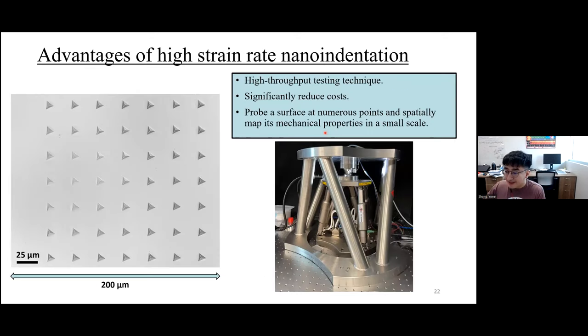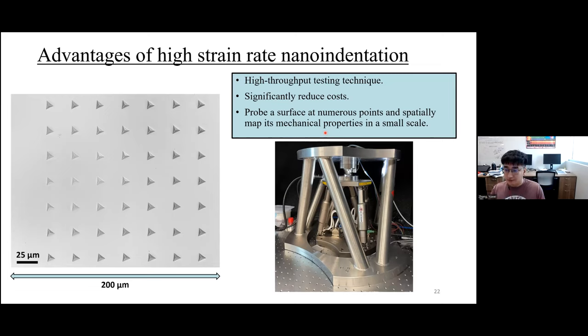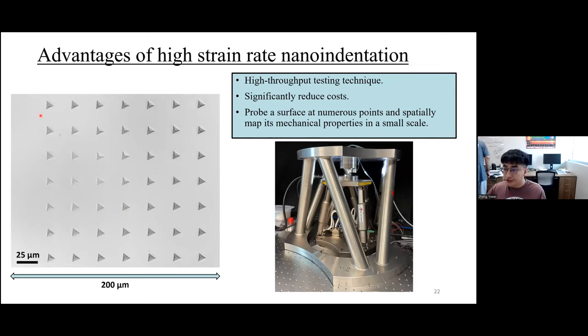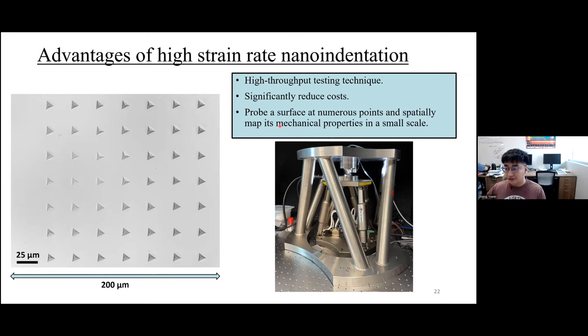In summary, we have provided comparisons between our high strain rate nanoindentation platform and traditional high strain rate testing through both TEM observation and quasi-static reloading. The advantages of our platform include high-throughput testing — all 49 indents shown were produced within one hour, with each indent taking about one minute. All indents were produced within a 200 by 200 micron region, which tremendously decreases sample preparation costs. Finally, our technique can probe a surface at numerous points and map mechanical properties at the small scale. This completes my talk today. Thank you.